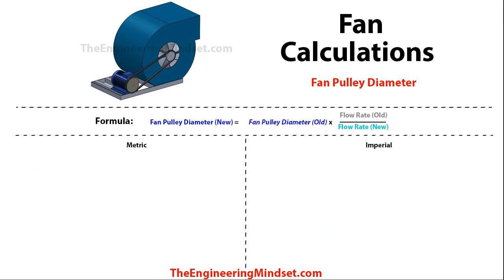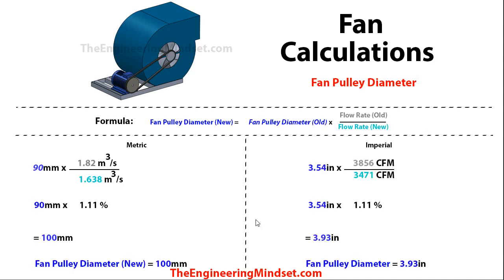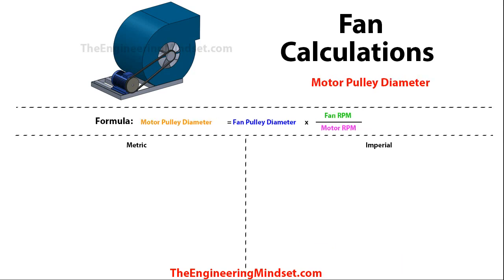Another way to calculate this is if the flow rate has changed — say half the floor has been cleared and you want energy savings. The formula is: new fan pulley diameter = old fan pulley diameter × (old airflow rate ÷ new airflow rate). Using a 10% reduction from the design data, the division gives a ratio of 1.11. Multiplying by the original fan pulley diameter gives a new diameter of 100 mm (3.93 inches).